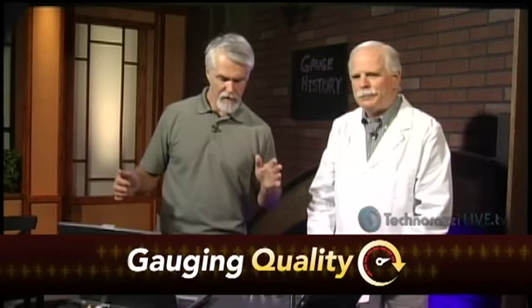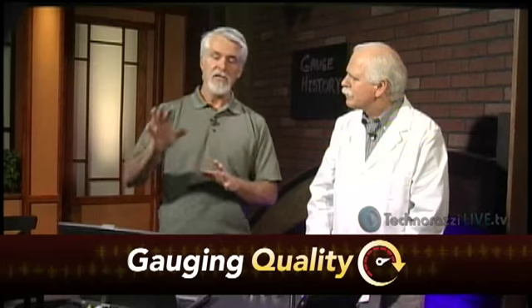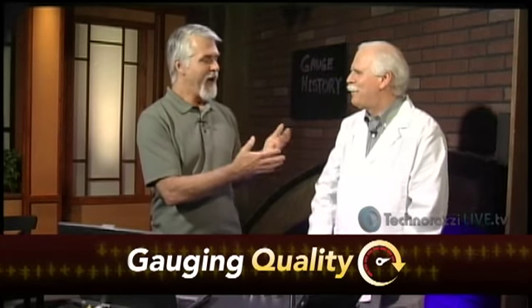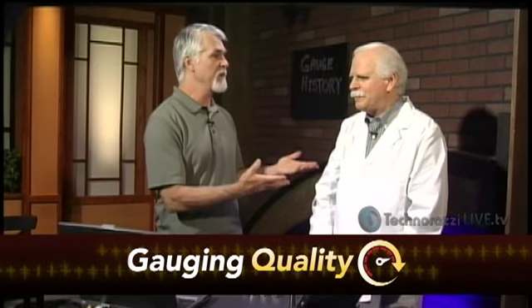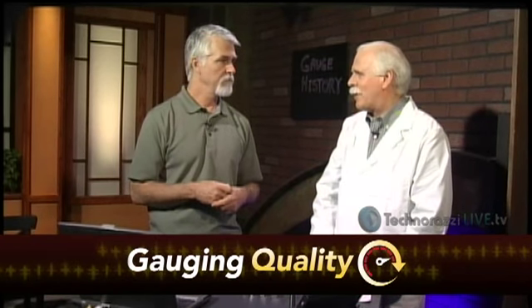Now, I think we've hit on the high points of what we can get from calibration history. We talked about doing this in software. Tell us, in the old days, a couple years ago, how would you have gotten a calibration history? What would the manual method have been? The manual method would usually be printing out the certifications, looking at the history, making a graph on graph paper or in Excel, something like that, connecting the lines.